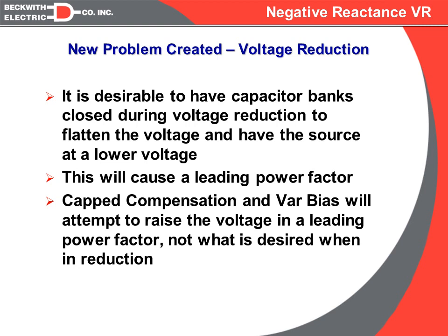And as we saw before with the capped compensation and VAR bias, a leading power factor induces the regulator or LTC to raise the voltage, which is counteractive to what we want by issuing a voltage reduction command.